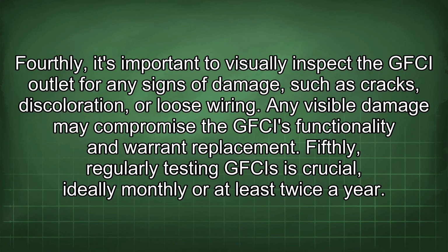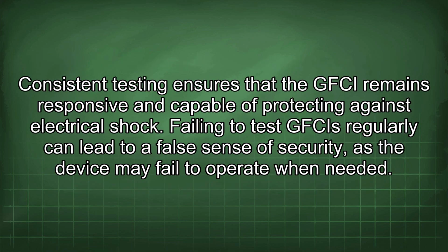cracks, discoloration, or loose wiring. Any visible damage may compromise the GFCI's functionality and warrant replacement. Fifthly, regularly testing GFCIs is crucial, ideally monthly or at least twice a year. Consistent testing ensures that the GFCI remains responsive and capable of protecting against electrical shock.